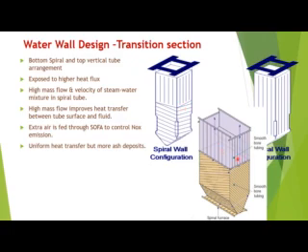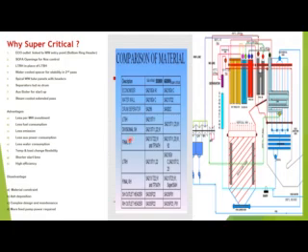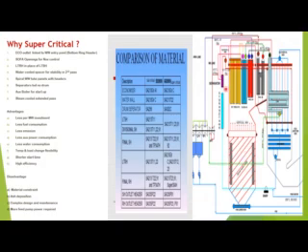The SOFA supplies additional air to reduce NOx products. Looking at the basic differences from subcritical: the economizer outlet is connected directly to the inlet header of the water wall, whereas in subcritical it passes through a drum. SOFA is available here; in subcritical there is an LTSH zone in the back pass, but here it is LTRH. With the spiral water wall, instead of a drum they use a separator, up to a load capacity of 30 to 40 percent.